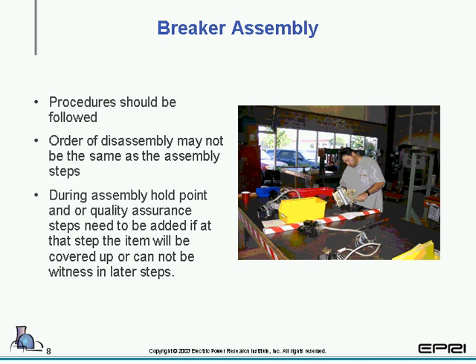We're moving on to the last part of it, assembly. Just because you take it apart one way does not necessarily mean you want to assemble it in the same order you took it apart. Typically, most people can take anything apart, but it's important that when you get to a certain step where the parts cannot be seen later on, because they're put inside a container or a subassembly built up into a larger subassembly, that there's some sort of check or quality assurance, or another qualified technician looks at that part before those subassemblies are put together and then built up to a larger subassembly and then to a breaker.